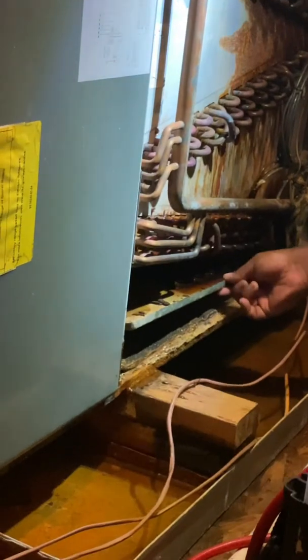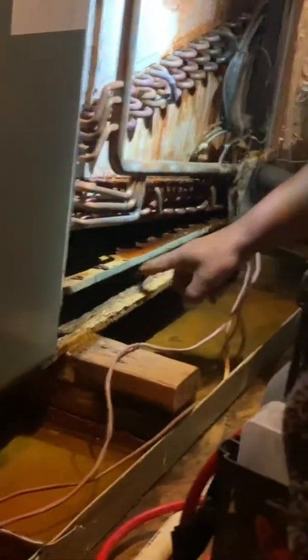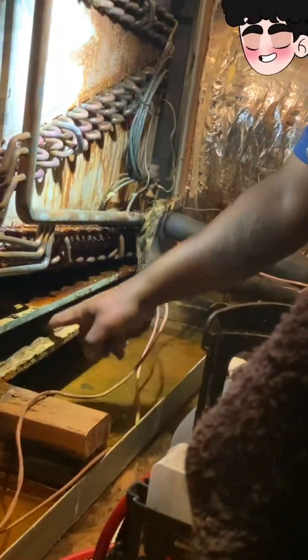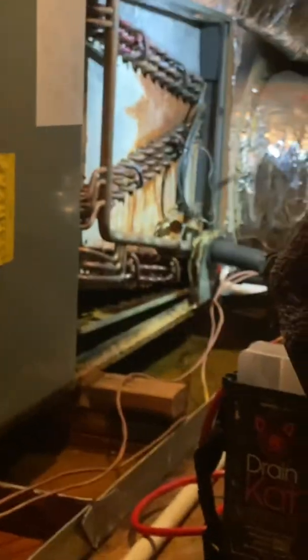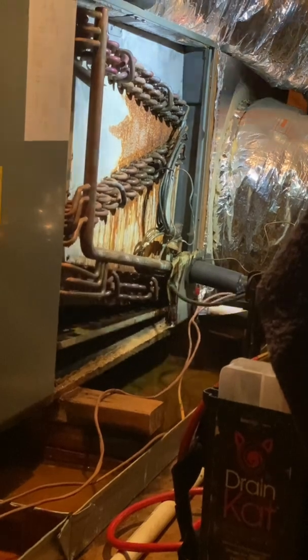So when the main drain line is clogged, this pan will fill up and then start to overflow — and this is what happens. This will take some time to dry out. That one's supposed to be dry. Leak detector — what it does is it detects and picks up the refrigerant.